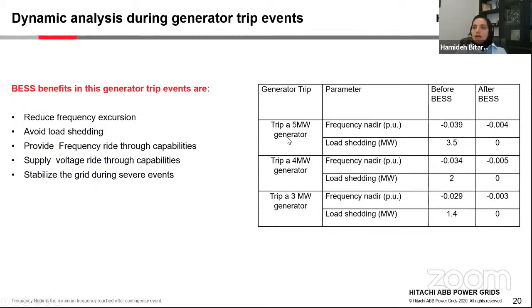When we tripped a 5 megawatt generator before the BESS, we had load shedding again from our protection system to sustain the frequency within allowable limits. Frequency nadir is a technical term related to the minimum frequency that happens after the contingency. So let's see what happened after we integrated the BESS.